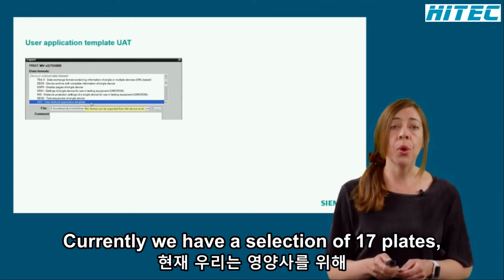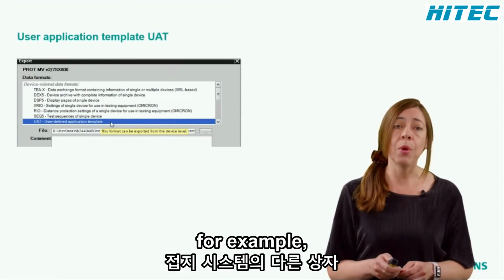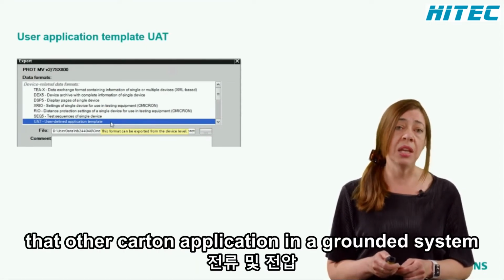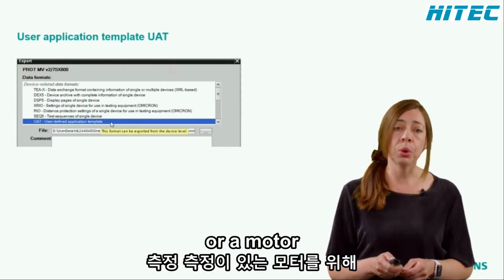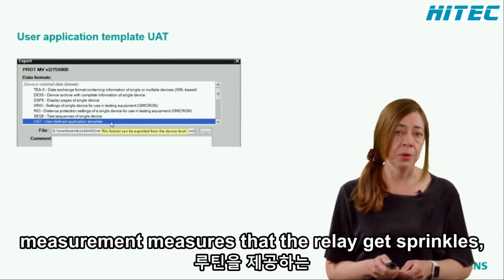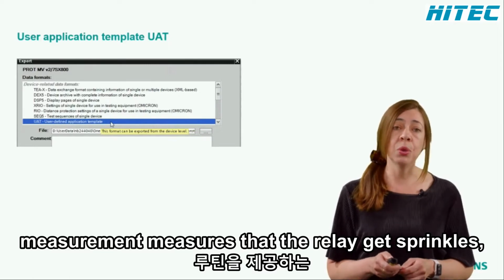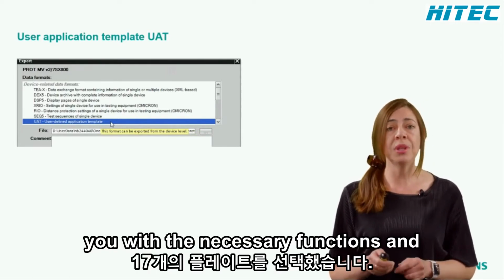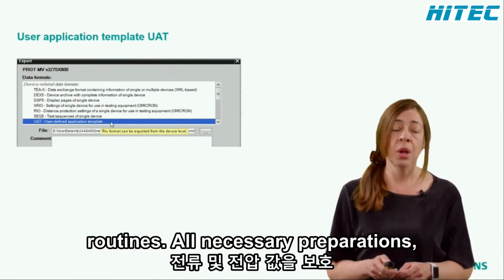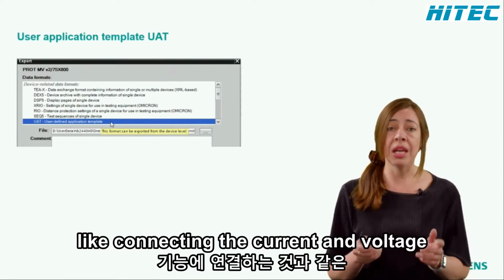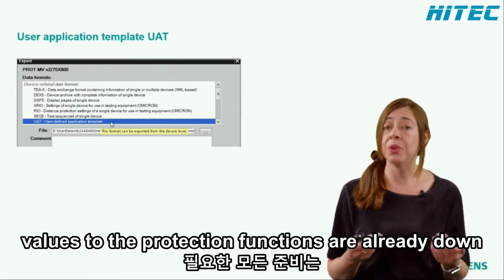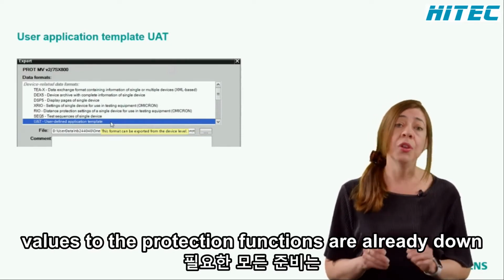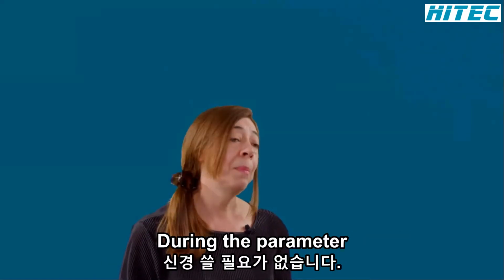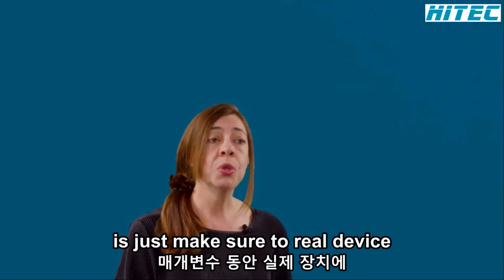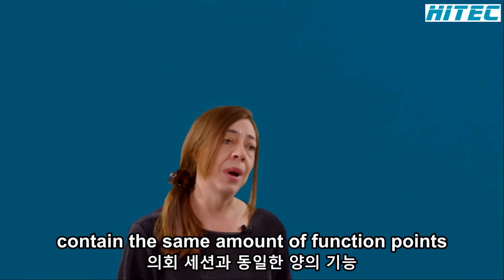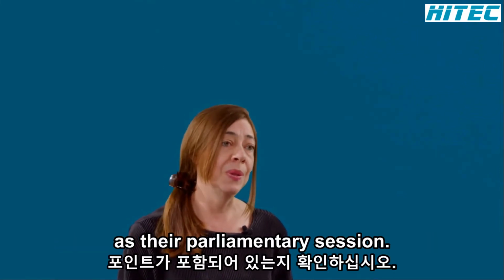Currently, you have a selection of 17 templates, for example, for a directional overcurrent application in a grounded system or a motor with current and voltage measurement. DIGSI 5 makes sure that the relay gets pre-configured with the necessary functions and routings. All necessary preparations, like connecting the current and voltage values to the protection functions, are already done, and you don't need to take care about them during the parameterization. Just make sure your real device contains the same amount of function points as the parameterization.